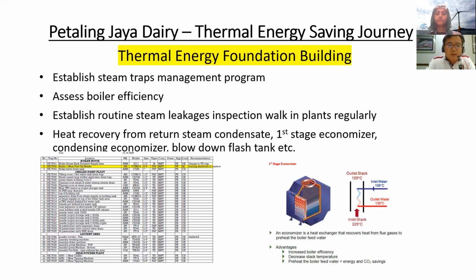For heat recovery, we are doing return steam condensate, first stage economizer, condensing economizer, also better known as second stage economizer, and blow down flash tank. These are the technologies which we are using. For the first stage economizer, from the picture below, an economizer is a heat exchanger that recovers heat from flue gas and preheats the boiler feed water. The advantages are increased boiler efficiency, decreased stack temperature, and improved overall performance. Next slide, please.